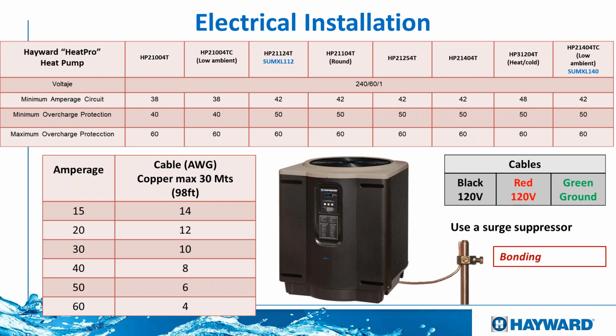So what I want to say with this is that if we go with a 50 amp breaker, we're going to require a number 6 AWG wire. That wire is going to guarantee that it's big enough to support the amount of amperage, the amount of heat, so it won't burn out. Now, if we go with 60 amps, then we're going to have to go down to a number 4 wire. So follow these instructions. This is going to guarantee a better installation.